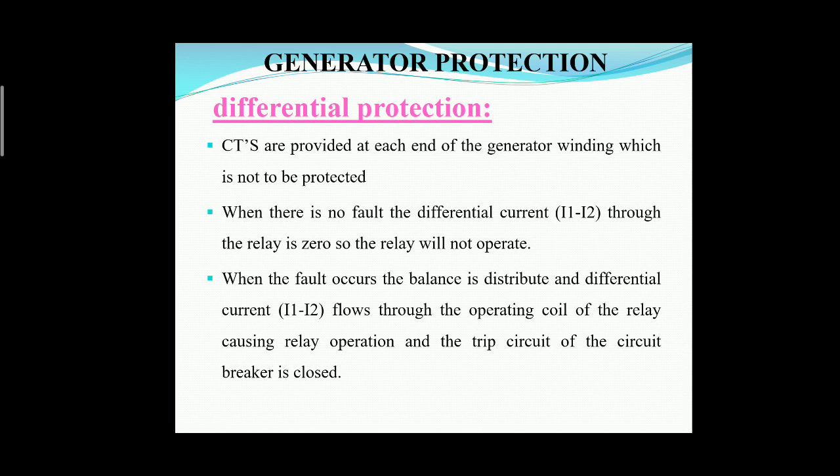Any internal faults inside the stator winding are cleared mainly by differential protection. If any internal faults are obtained in the stator winding, they are cleared mainly by the differential protection scheme of the generator or alternator. It is employed for the protection of the stator winding of the generator against earth faults and phase to phase faults.